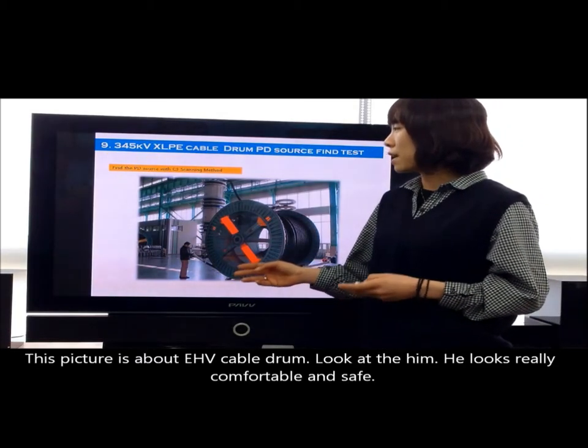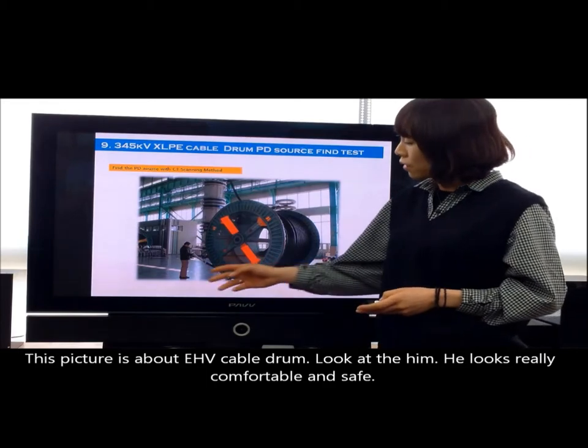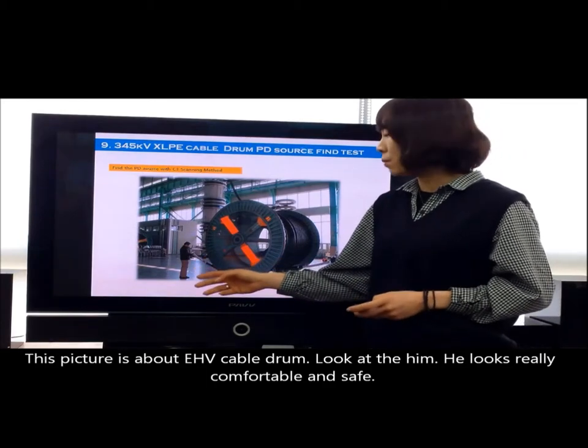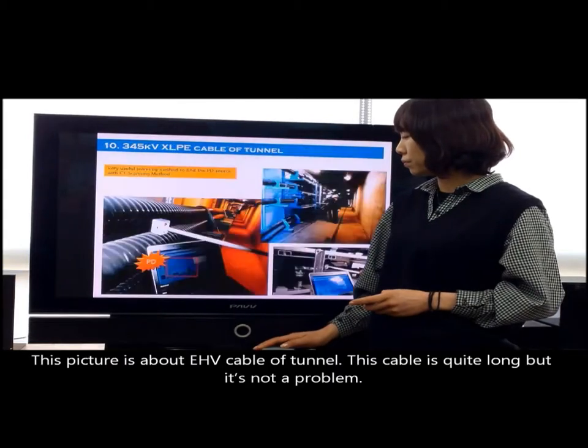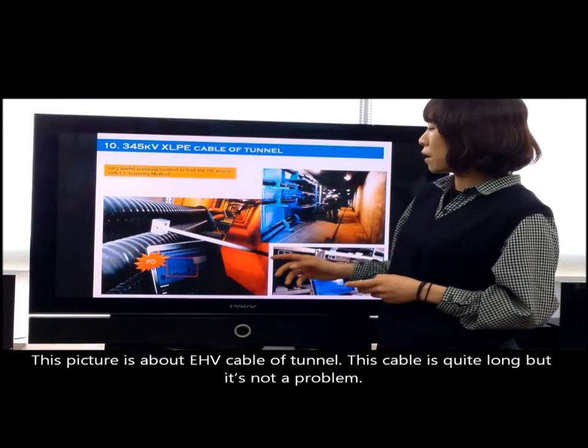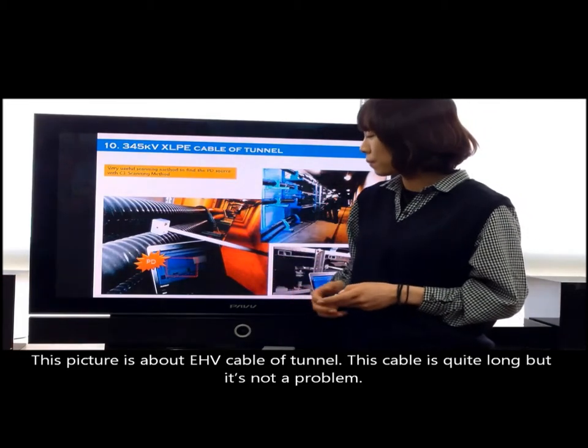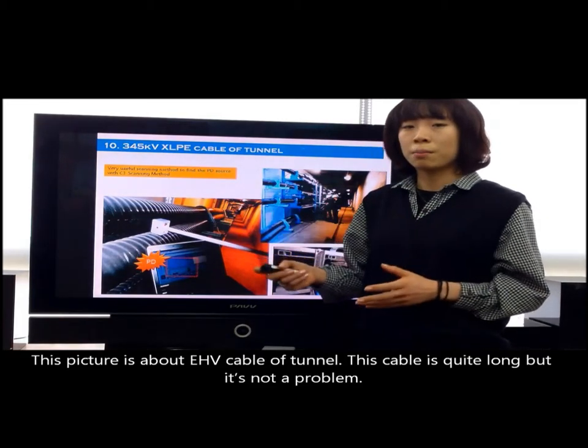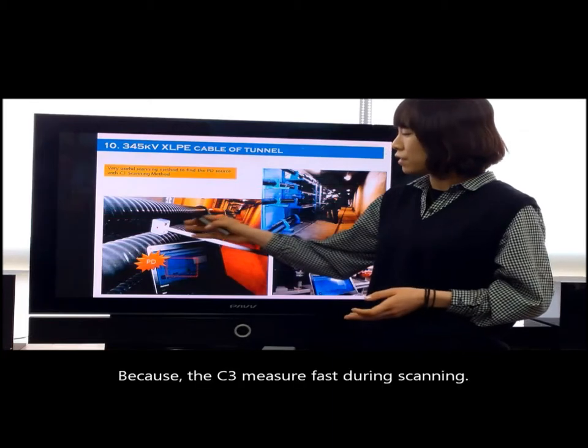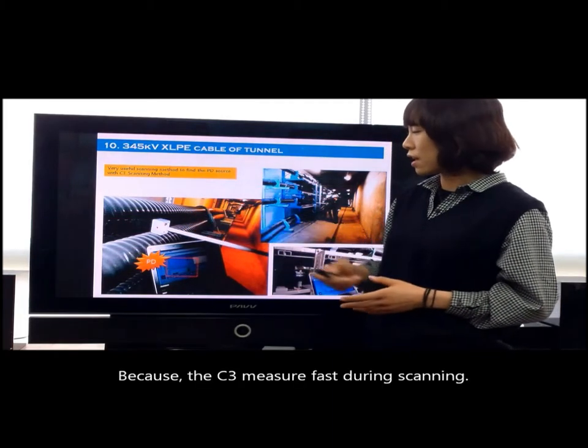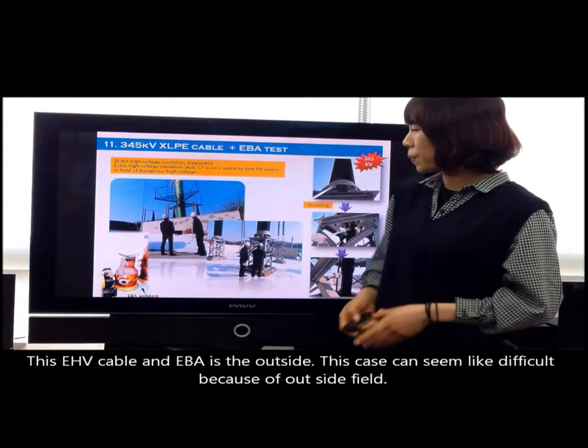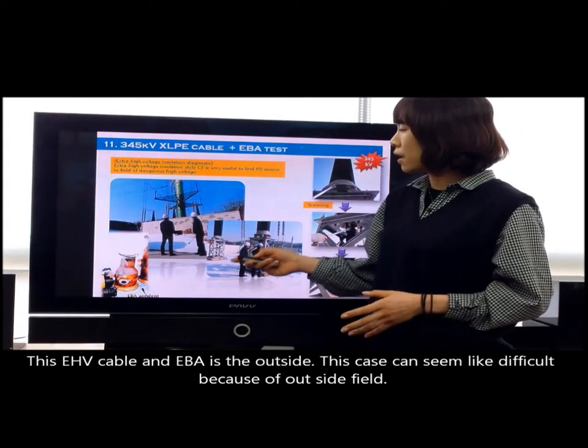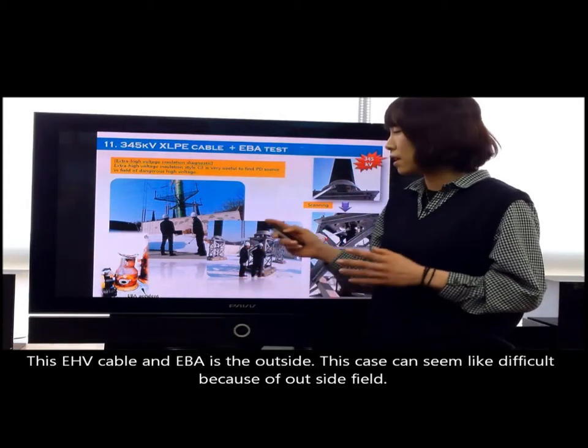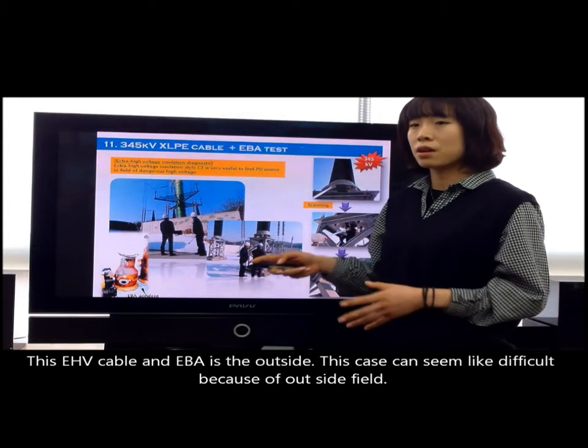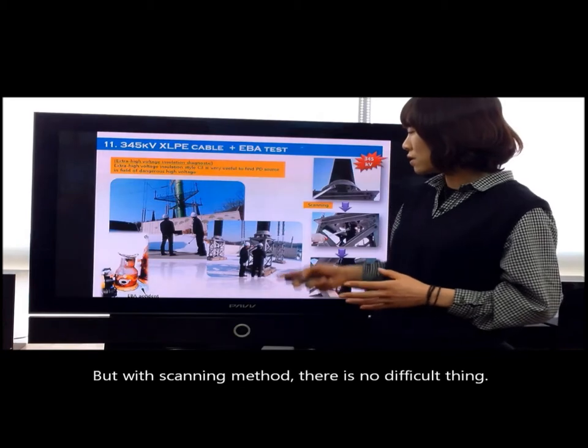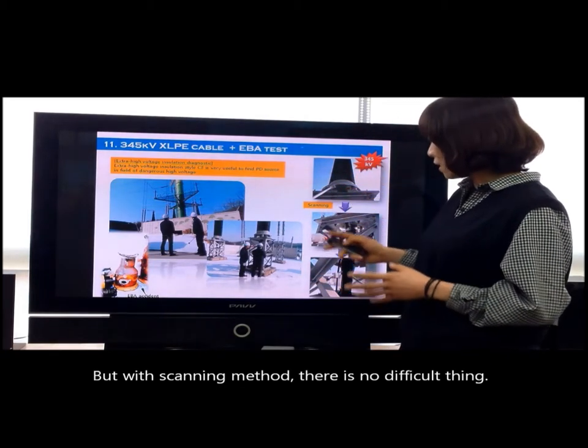This picture is about an extra high voltage cable drum. Look at him. He looks really comfortable and safe. And this picture is about an extra high voltage cable in a tunnel. This cable is quite long, but it's not a problem because C3 measures fast during scanning. This extra high voltage cable and EBA is outside. This case can seem difficult because of the outside field, but with the scanning method, there is no difficulty.